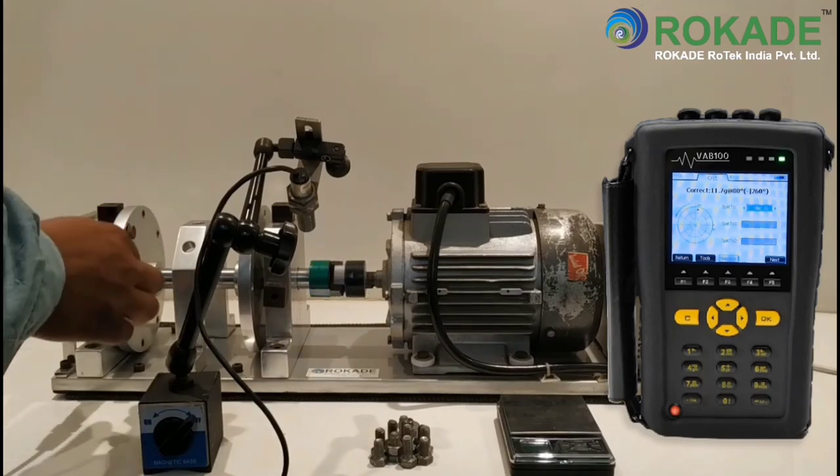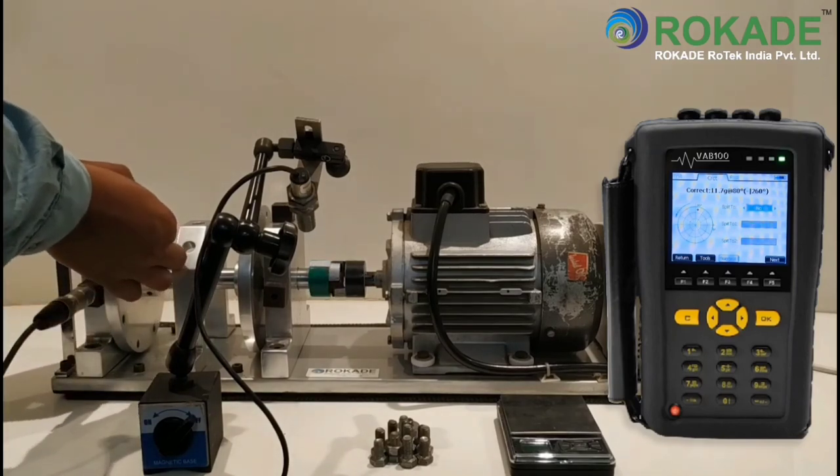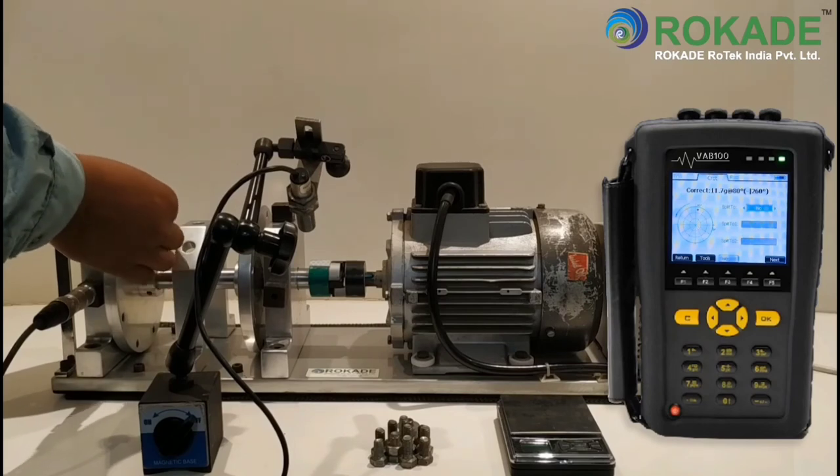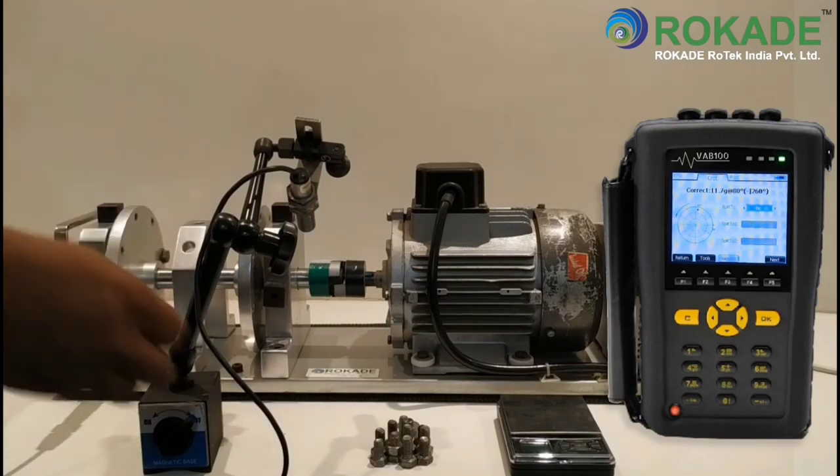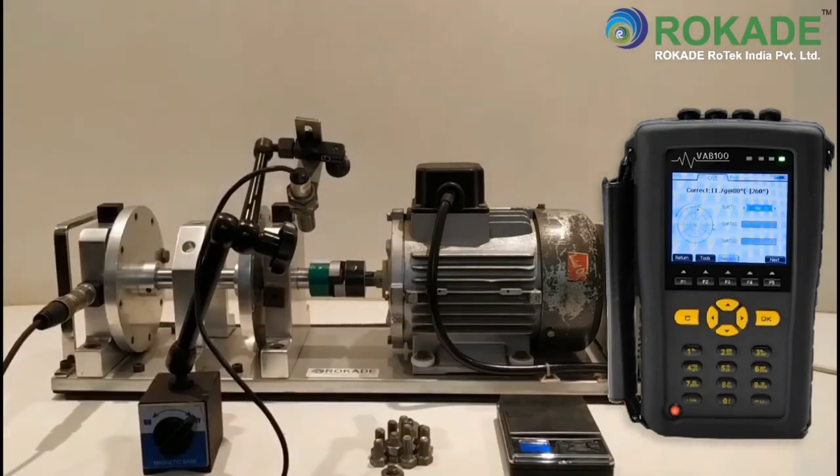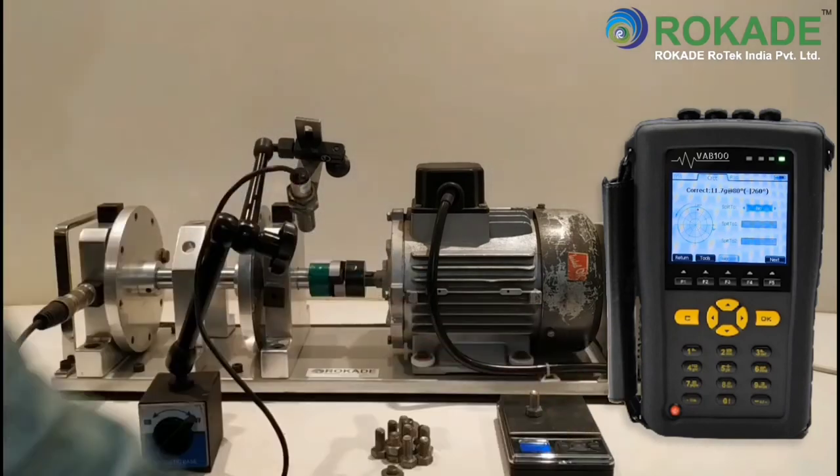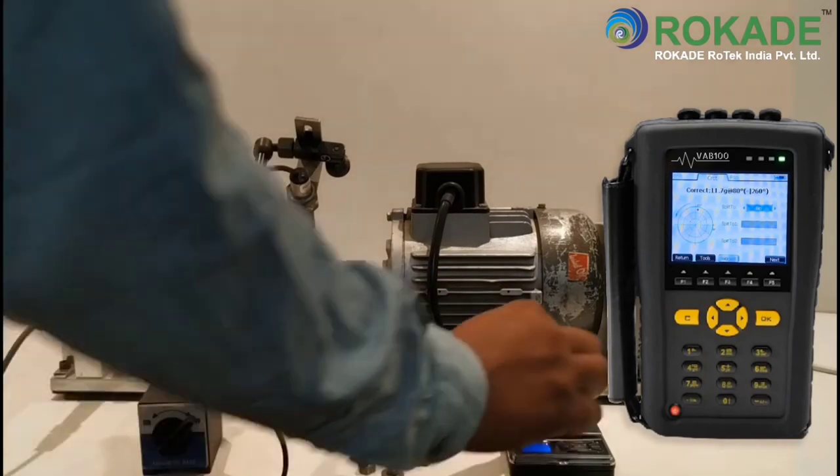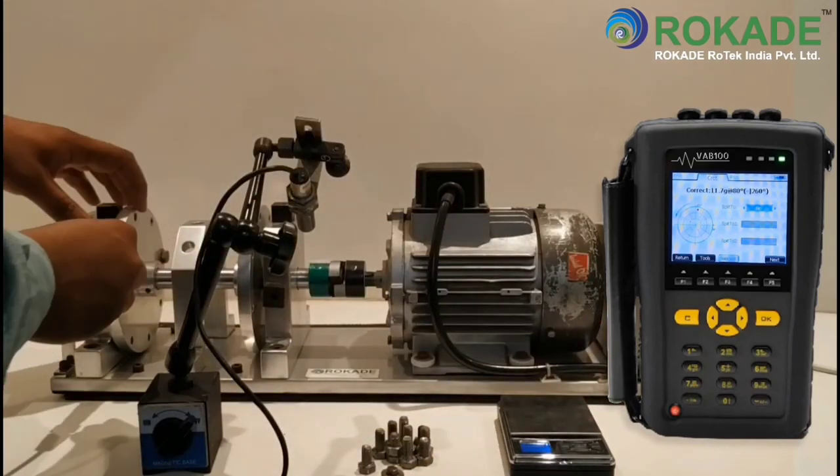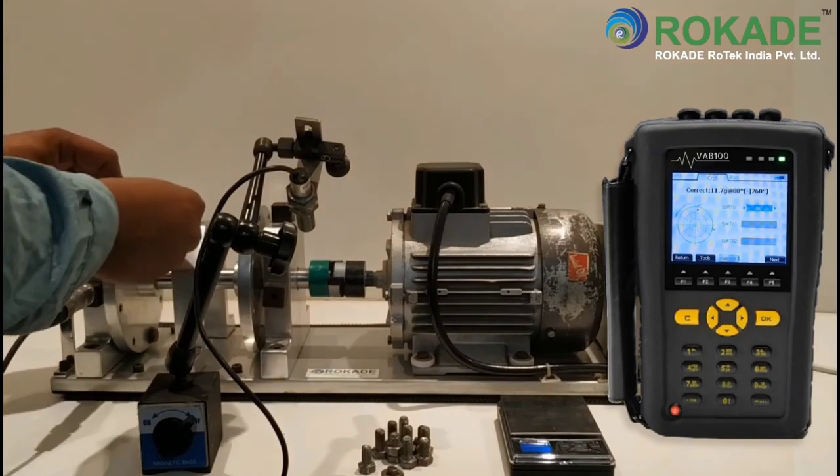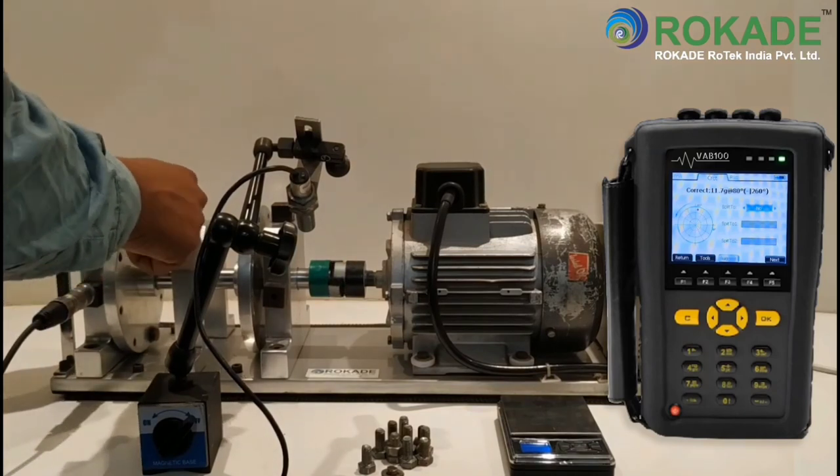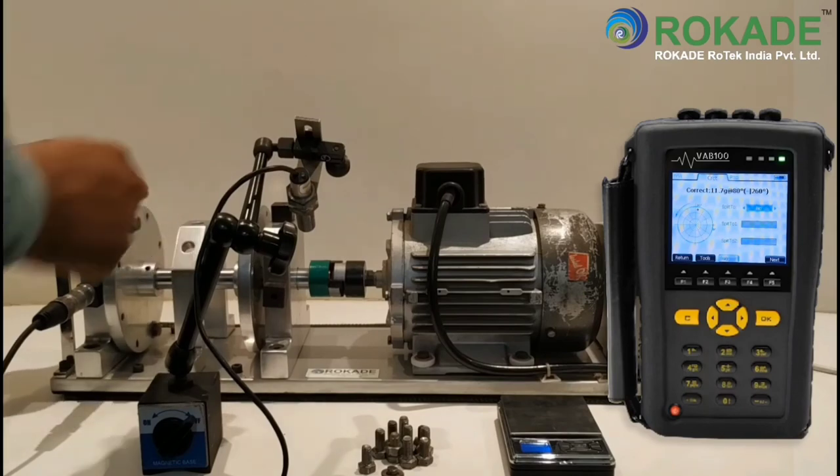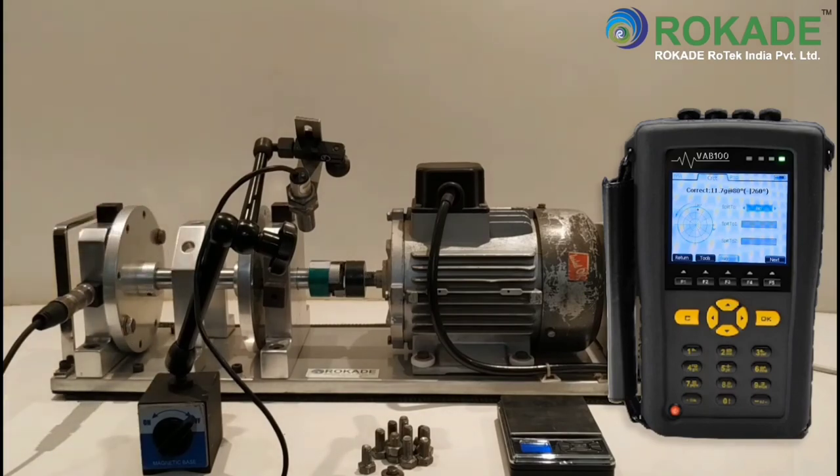Remove the trial weight. Add the correction weight by marking the degree from trial mass that is zero degree. Now again start the machine.